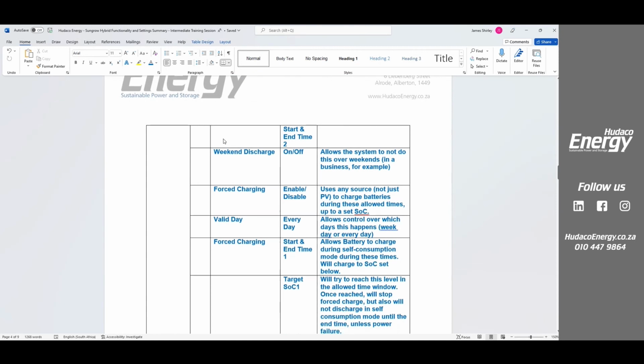So we call that the weekday discharge or charge. And we can also have for weekend, same. We can turn it on and off if we want it to be different for weekday or weekend. That's discharging, in other words, using the battery power during certain times. Of course, if there's load shedding, the battery will immediately kick over. By the way, this is for self-consumption mode. So if there was load shedding, it would discharge already.